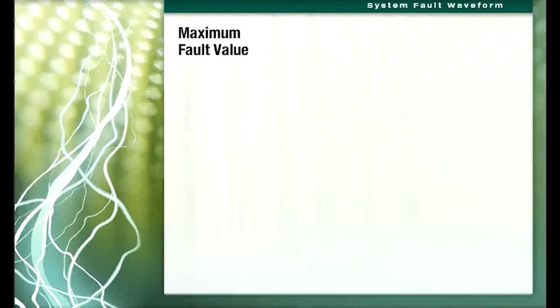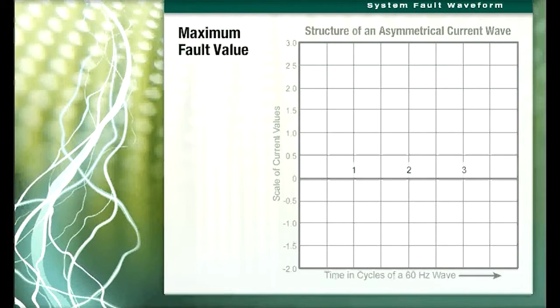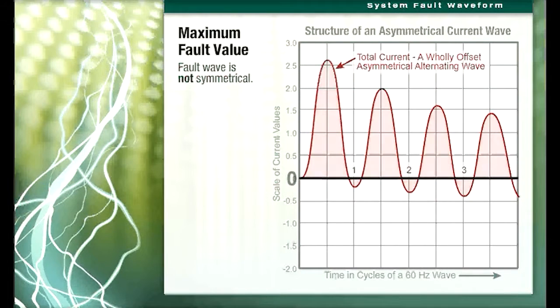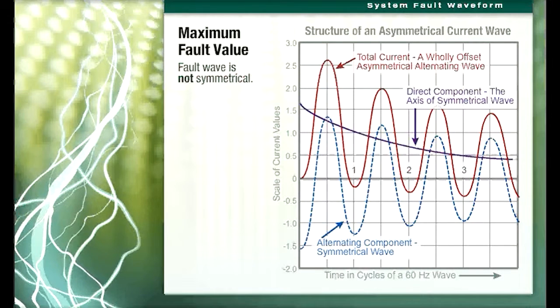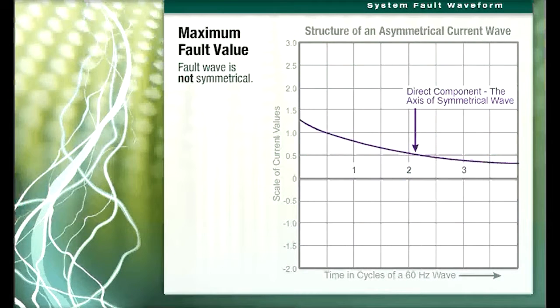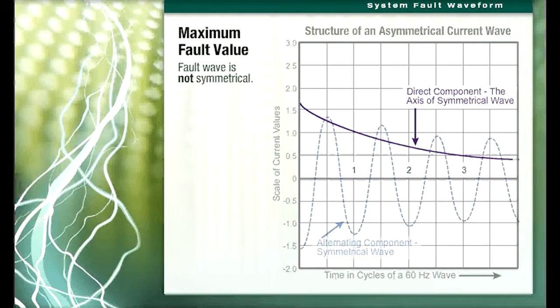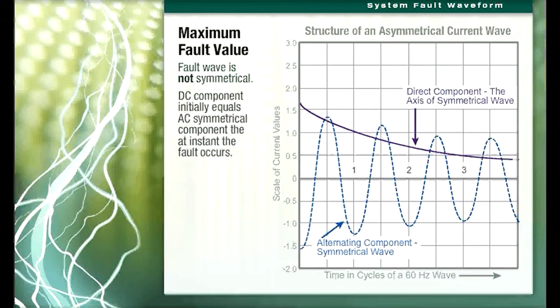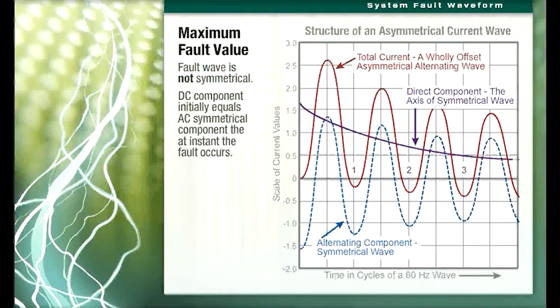In determining the maximum value of fault current at some point in a system, it should be noted that the fault current wave is not symmetrical about the zero current axis for several cycles after the fault occurs. This asymmetrical fault current wave is composed of two components: the symmetrical fault current and a direct current component whose magnitude is determined by the point on the voltage wave at which the fault occurred. The magnitude of the DC component can vary from zero to a maximum equal to the peak of the symmetrical AC component. At any instant after the fault, the magnitude of the total asymmetrical current is equal to the algebraic sum of the symmetrical AC and the exponentially decaying DC component.